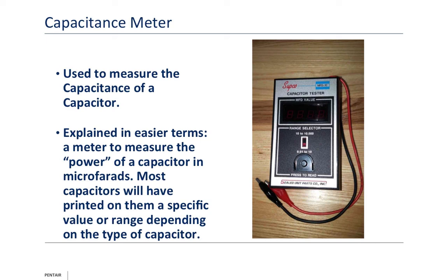Now, a lot of guys tell me they don't bother looking at capacitors because, Dan, you can tell when they're bad. Not always. If a pump is buzzing or humming, especially when the motor starts to get warm and it's cycling, that's where capacitors that are a bit weak can be the key issue.